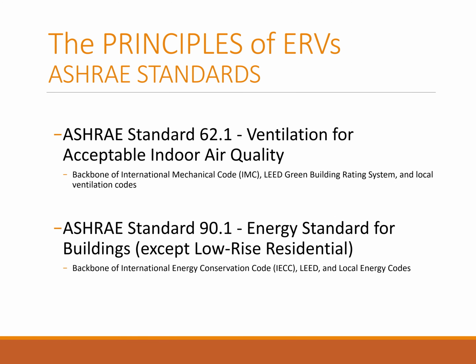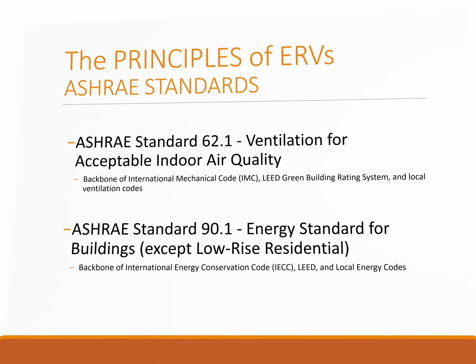ASHRAE standards drive building codes. Many local, state, and national governments require code enforcement on new construction. ASHRAE Standard 62.1 is concerned with ventilation for acceptable indoor air quality and is widely used in the HVAC industry. ASHRAE Standard 90.1 is the energy standard for buildings. Use of energy recovery products help building owners to meet these codes, such as the LEED Green Building Rating System and the International Energy Conservation Code, or IECC.